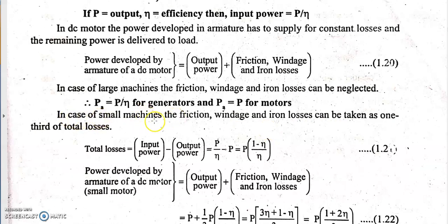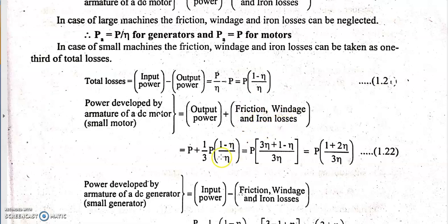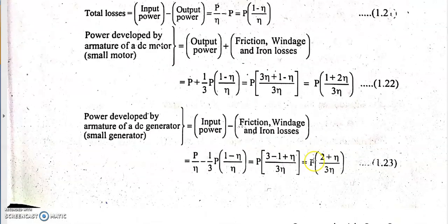For small capacity machines, friction, windage, and iron losses are taken as one-third of the total losses. Total losses equal input power minus output power, that is P/η − P = P(1−η)/η. One-third of this is the friction, windage, and iron losses. Combining these with the output power, we get expressions for PA for small machines.